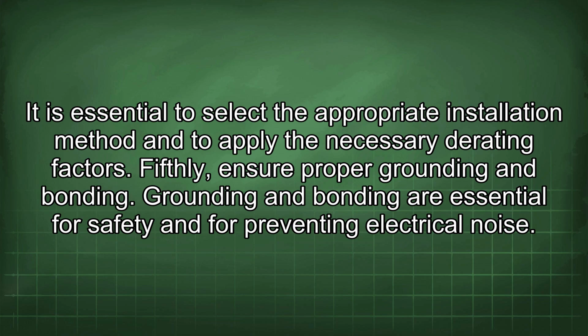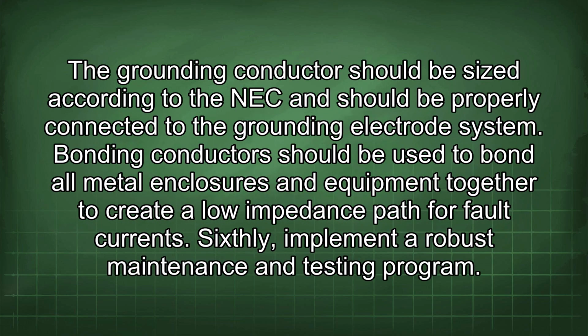Fifthly, ensure proper grounding and bonding. Grounding and bonding are essential for safety and for preventing electrical noise. The grounding conductor should be sized according to the NEC and should be properly connected to the grounding electrode system. Bonding conductors should be used to bond all metal enclosures and equipment together to create a low impedance path for fault currents. Sixthly, implement a robust maintenance and testing program.